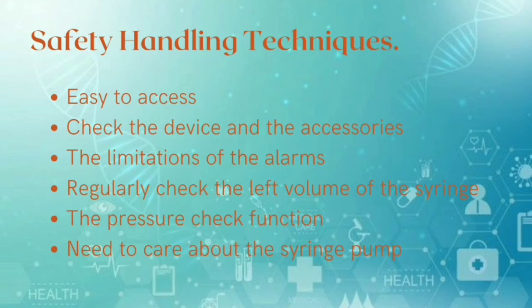it is easy to access, and then check the device and the accessories before use. The alarms are not limited to the voice alarm system but also depend on the real clinical condition of the patient. To inject with the syringe pump to a patient, we need to check the remaining volume of the syringe regularly.